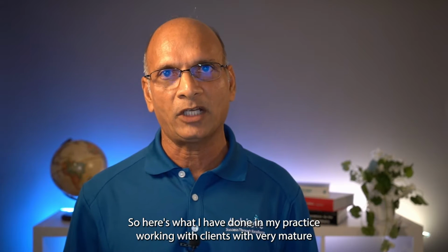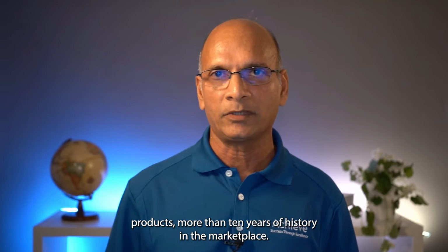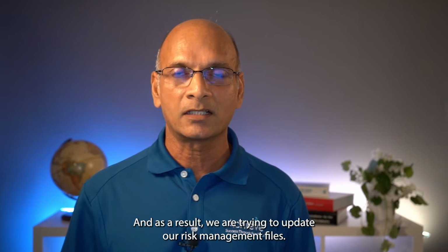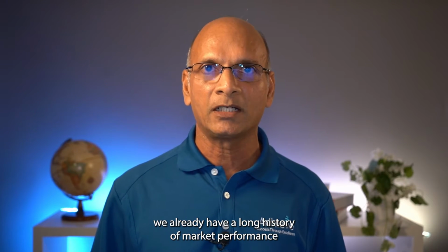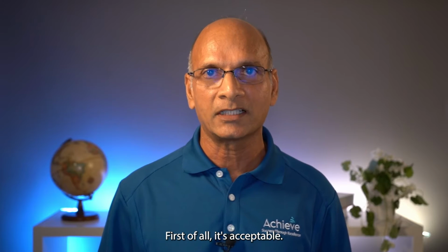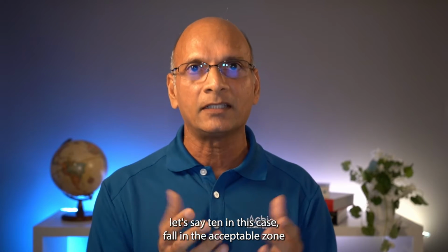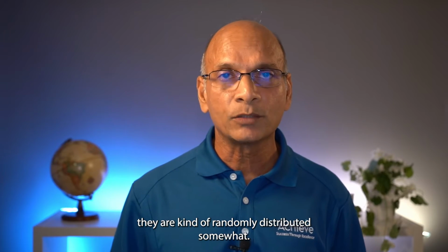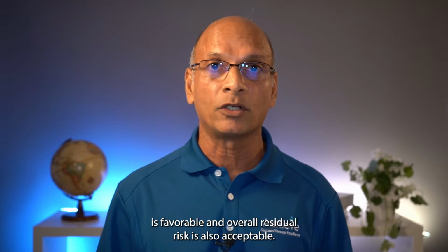So here's what I have done in my practice, working with clients with very mature products, with more than 10 years of history in the marketplace. Now we know that the 2019 version has some new requirements, so we may have to do some remediation, and as a result we are trying to update our risk management files. In those scenarios, we already have a long history of market performance and we know the overall benefit-risk level is acceptable, first of all. So we make the determination that if all individual residual risks, let's say 10 in this case, fall in the acceptable zone and they are not clustered in a certain area, they're kind of randomly distributed, we make the judgment that our overall benefit-risk is favorable and overall residual risk is also acceptable.